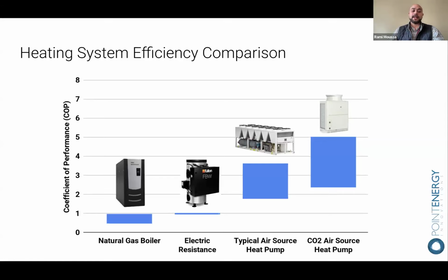So what we most frequently utilize for an energy-efficient and power-efficient approach to electrifying buildings is heat pumps. And it's not magic - it's the refrigeration cycle - but with every unit of energy we put into that system, we get 2 to almost 4 units of heat out. So 2 to 4 times as efficient as electric resistance. With that, we can reduce the amount of power needed in our electrical infrastructure and in our increased distribution to that new equipment, and that creates a more viable solution to electrify our buildings today.